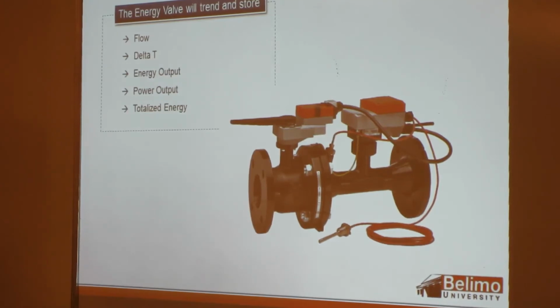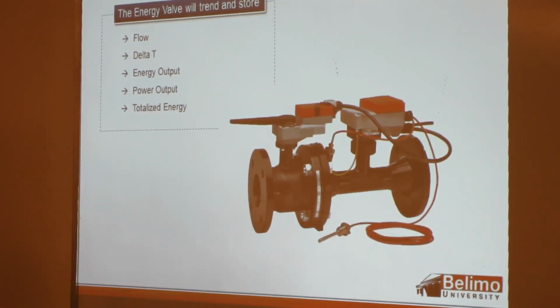Now, with this product, I see this product as being specific to certain applications, certain jobs, from the standpoint that if you don't have somebody that's going to be looking at the reports that can come out of this valve at least a couple times a year, you're probably wasting your money because you're paying for something that you're not using. You'd be better off going with the EPIV at that point, because pressure independent valves in general are good for all applications. There's no need to go view any kind of reports or anything.